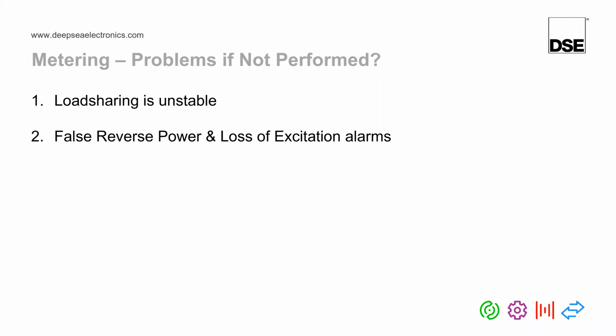And we've had one last question come in saying, the power system is Delta 3-phase 3-wire. Do we need to remove the neutral connection in the controller? Well, if it is a true 3-phase 3-wire Delta system, there is no neutral coming from your generator. Therefore, you do not connect it. The DeepSea module does not need a neutral connection to work. So if you have a 3-phase 3-wire Delta system, which natively does not have a neutral, you do not connect anything to the neutral terminal.